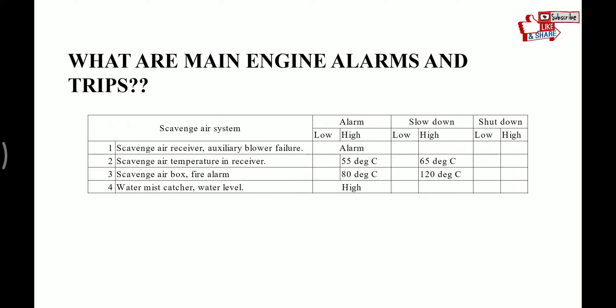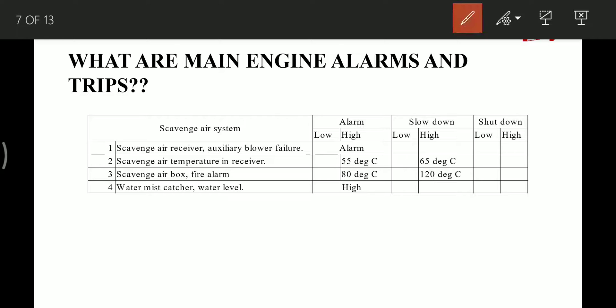The scavenge system: scavenge receiver auxiliary blower failure gives alarm. Scavenge receiver temperature — high alarm at 55°C and slowdown at 65°C. Scavenge box fire alarm — alarm at 80°C and slowdown at 120°C. Water mist catcher water level: gives high level alarm if water level in the catcher is high.